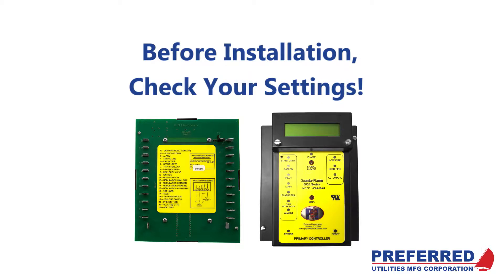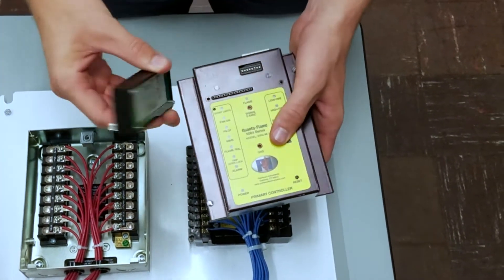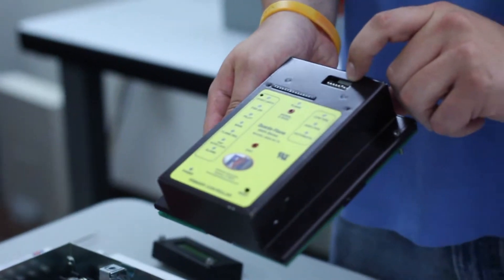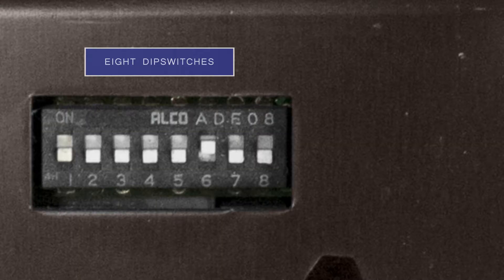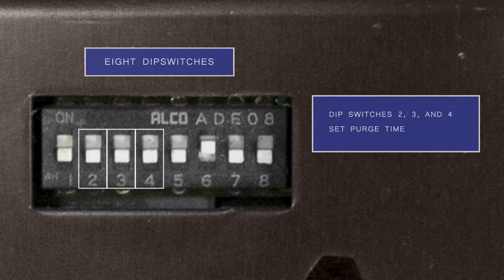Before installing your new 5004 M78 flame safeguard, there are a couple of settings we need to account for. The first of these is a series of dip switches located underneath the locally mounted LCD. Dip switch number one determines the action of the flame safeguard after a power failure. Dip switches two, three, and four are used to set the purge time for your Quanto-Flame flame safeguard.